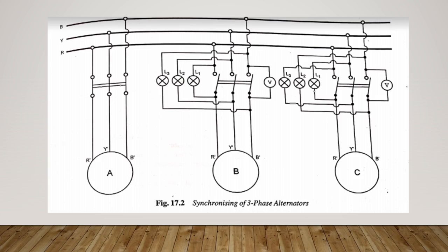So an additional condition which is met in the case of synchronization of a three phase alternator, apart from what we have seen for a single phase alternator, is that the phase sequence of the incoming machine should match with that of the system to which it is going to be connected. The process of checking the phase sequence and getting it corrected is known as phasing out of the alternator. Different methods of phasing out of an alternator are the three dark lamp method and the two bright and one dark lamp method. Now let us see the three dark lamp method.